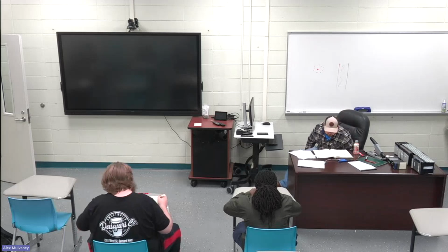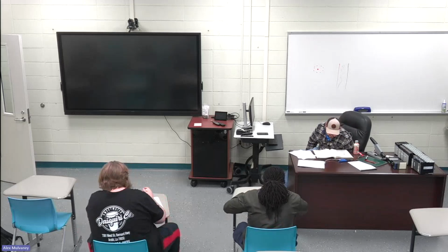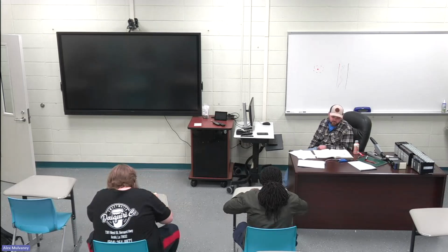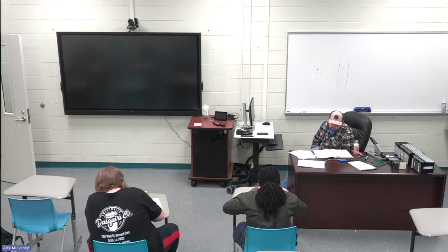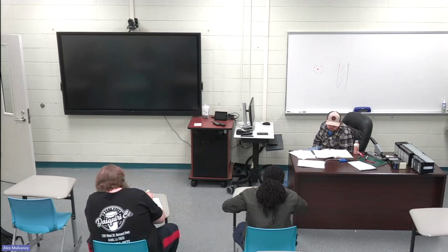Page 17, first paragraph, last sentence, long sentence. As such, the user of the instrument must be prepared to evaluate the extent of the noise, and then A, determine if the existing noise is not significant, B, eliminate the causes of unacceptable noise, or C, prevent the unacceptable noise from interfering with the instrument.